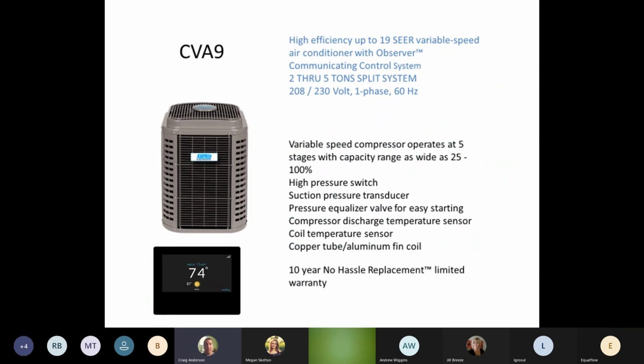So this is your fully modulating AC. This is only fully modulating if you group it up with a modulating furnace and a modulating stat. If not grouped up in that orientation, then this unit becomes a 2-stage air conditioner. We sell a lot of them as a 2-stage air conditioner because it's a very quiet unit. It's variable speed, ECM motors, all that stuff outside.